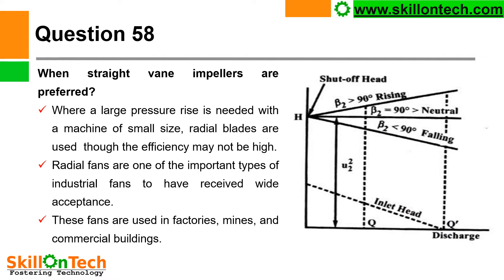Question 58: When are straight vane impellers preferred? Where a large pressure rise is needed with a machine of small size, radial blades are used, though efficiency may not be high. Radial fans are an important type of industrial fan used in factories, mines, and commercial buildings. You can see a picture showing shut-off head and discharge. The blade angle beta-2 greater than 90 degrees corresponds to forward curved vanes; beta-2 equal to 90 degrees is neutral (radial); and beta-2 less than 90 degrees corresponds to backward curved vanes.